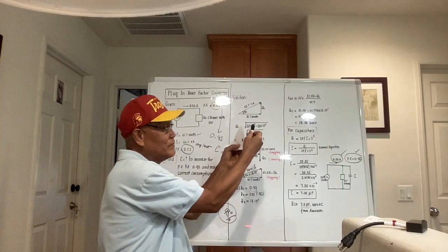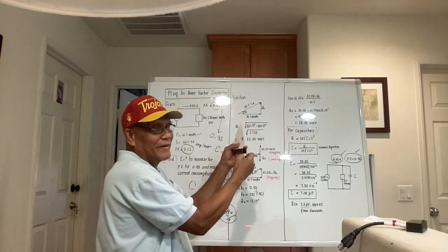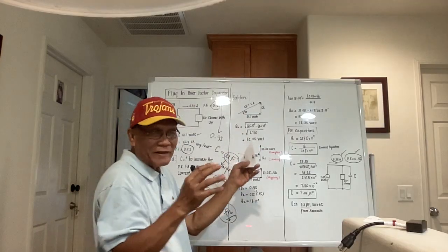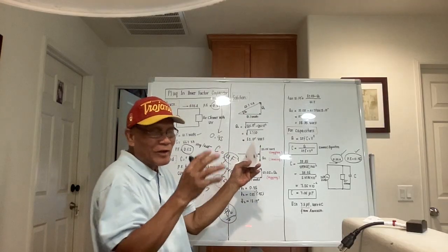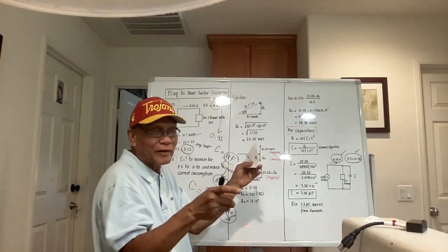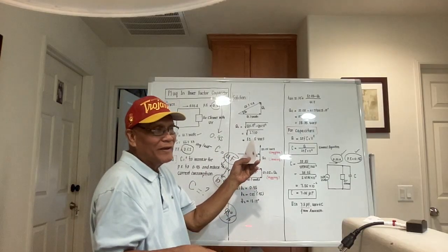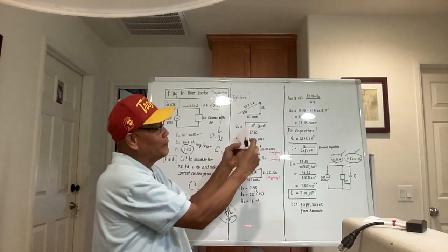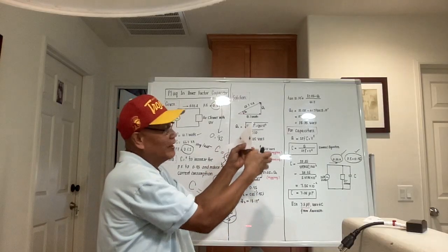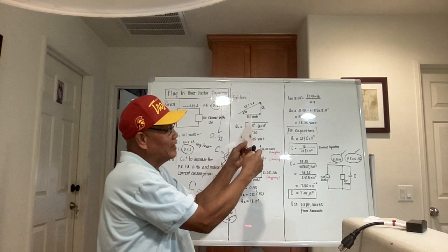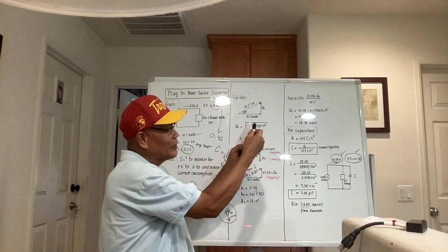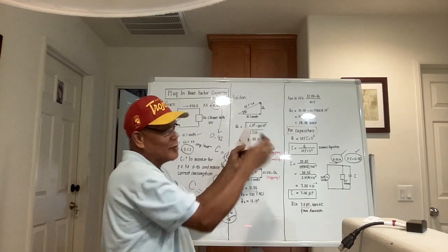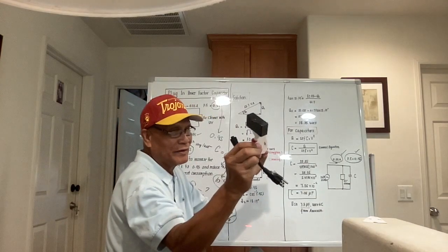This is positive and this is negative. So a positive and a negative will try to fight each other, and whichever is bigger will be the one who will win. So if we would like the resulting triangle to have a small Q, we put some capacitor here to lessen this total Q here. This is big, and to lessen this one, we must place a capacitor.